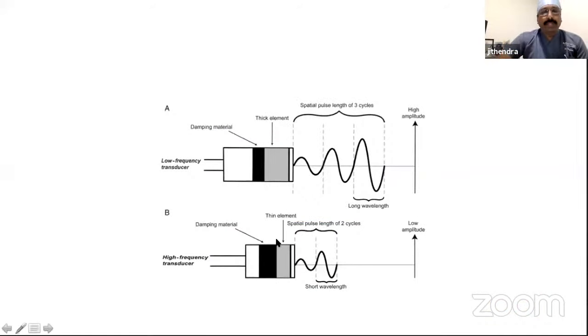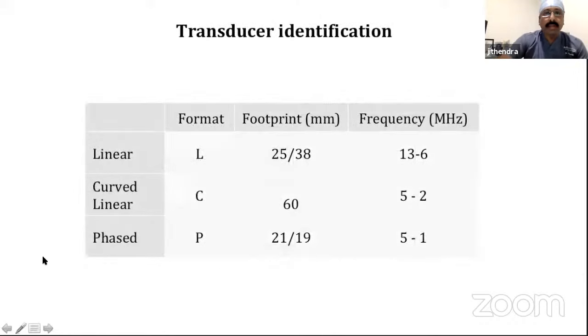Same thing I showed you earlier: there's a low frequency probe and a high frequency probe. The low frequency probe has an ultrasound with a long wavelength like this, with a spatial pulse length of 3 cycles, whereas for the high frequency probe the wavelength is short. You have a higher amplitude of the ultrasound waves for the low frequency, whereas it's a lower amplitude for the high frequency probe.